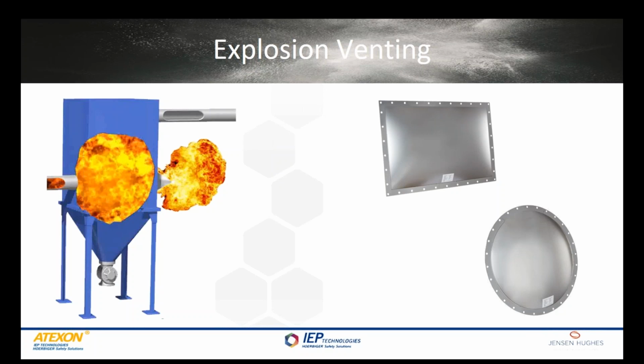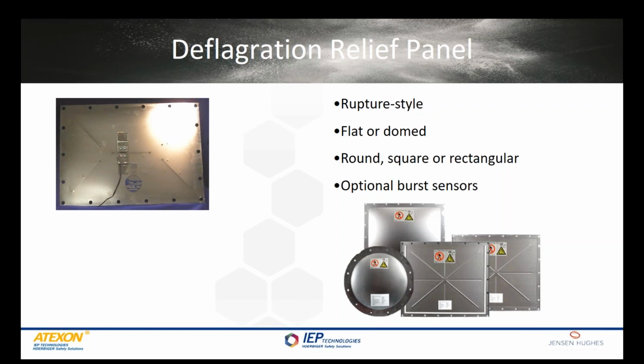Now, explosion vents come in quite a variety of sizes, styles and shapes. Some are rupture style vents. Other types of vents may be held on with frangible bolts. Some are spring loaded, some are magnetic latches. Vents can be flat, and some can be domed, especially in high pressure cycling applications. Dome vents tend to have a much longer service life. Vents can be round, square, or rectangular. Some vents can come with sensors that give a signal when an incident causes the vent to open, so you can stop the process and stop the spread of burning embers, sparks or fires to other parts of the process.